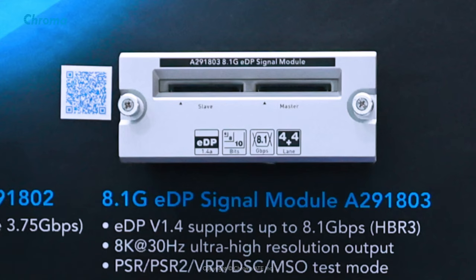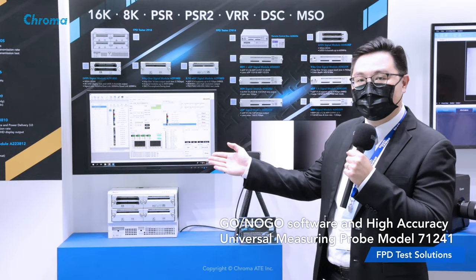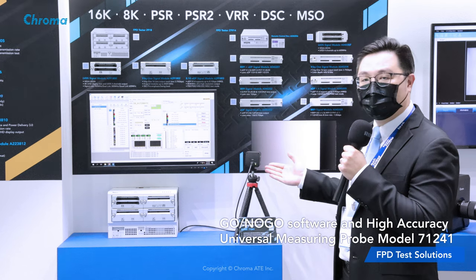It supports 8K at 30Hz and comes with built-in PSR, PSR2, VRR, DSC and MSO and other testing modes. It can be upgraded with Chroma software and combined with the Chroma 71241 for automatic luminance measurement of flat panel display. It also supports multi-display testing as well.